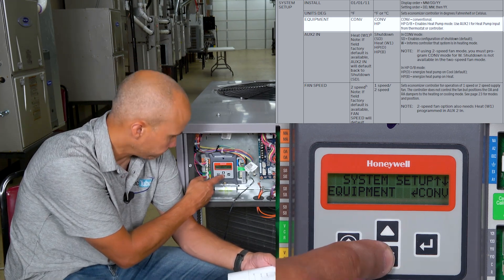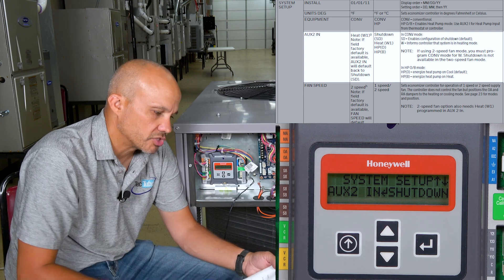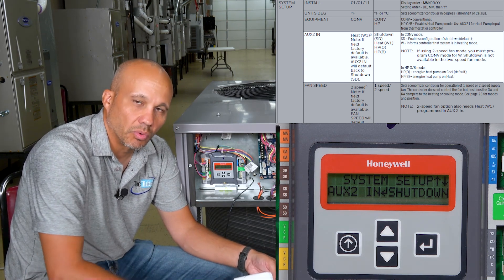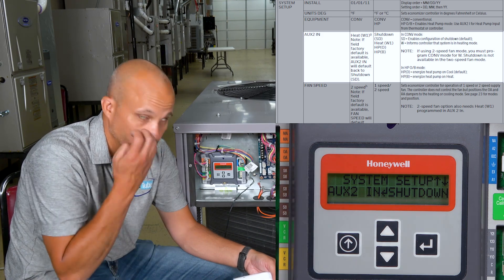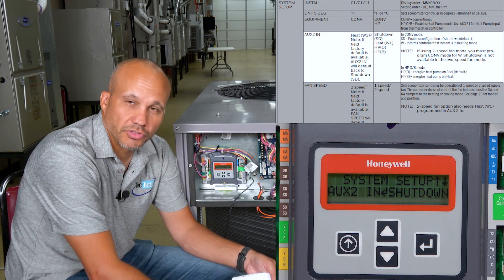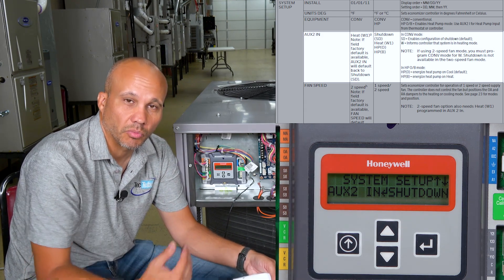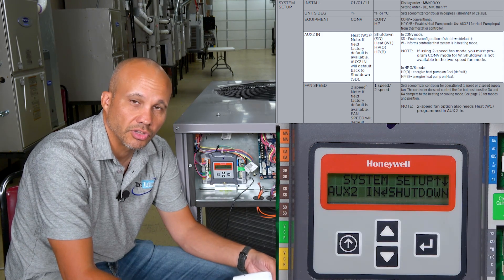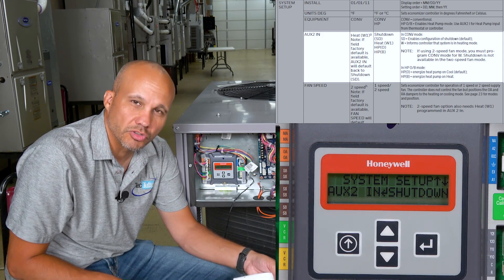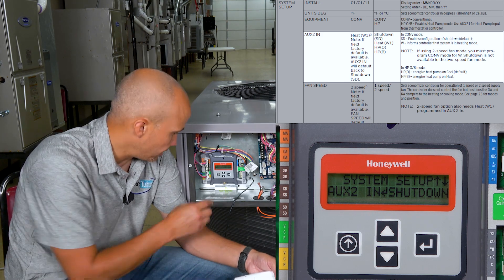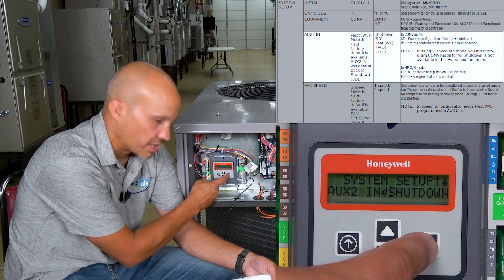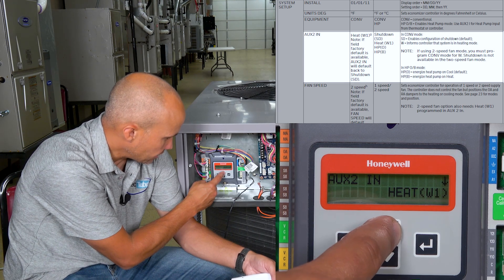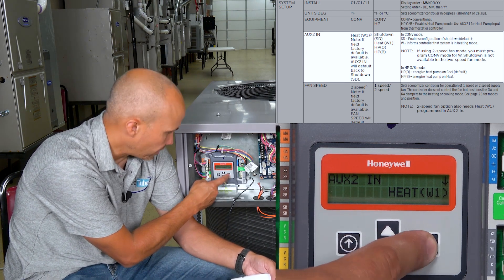Aux 2 Input is a flexible input on this controller for miscellaneous uses. Two of those relate to a heat pump. One is for shutdown — if you had a smoke detector wired to this, you can have it shut down the damper and shut off the unit. The one we're going to use in most applications is W, so I'm going to change this to W. I'll hit Enter, scroll until I get to Heat W1, and press Enter.